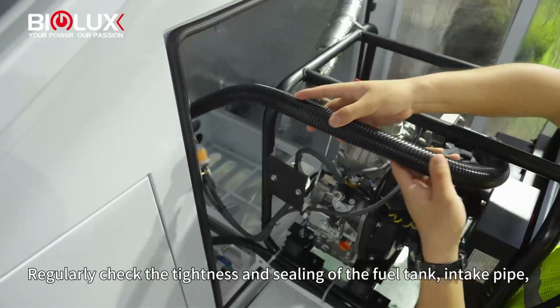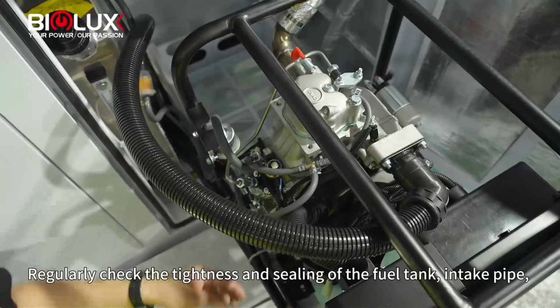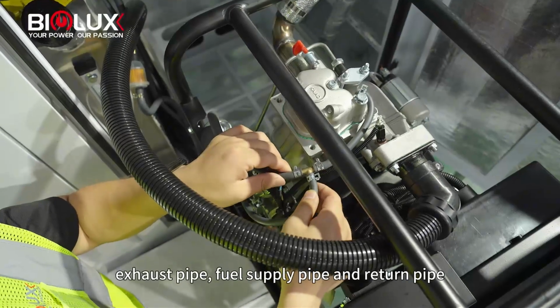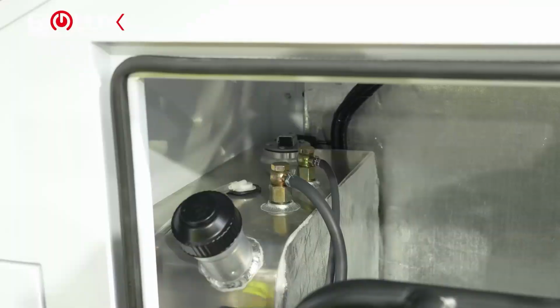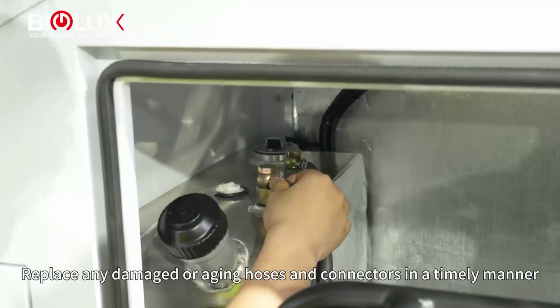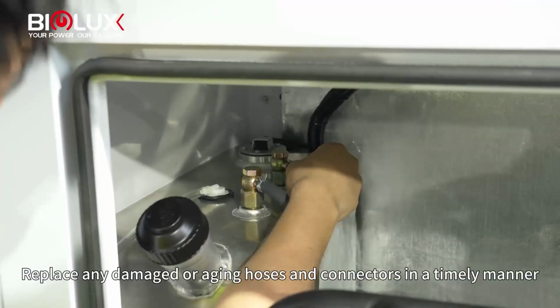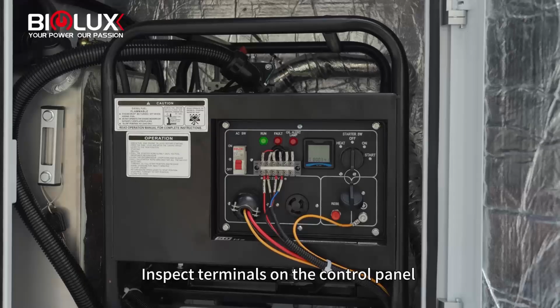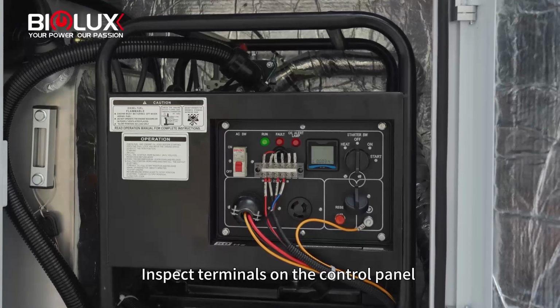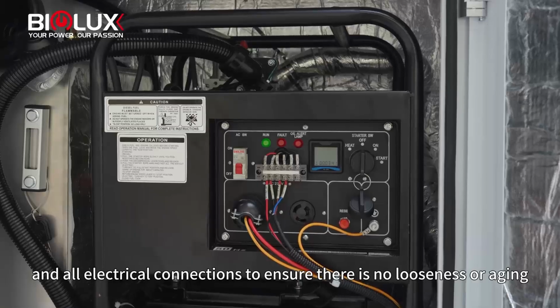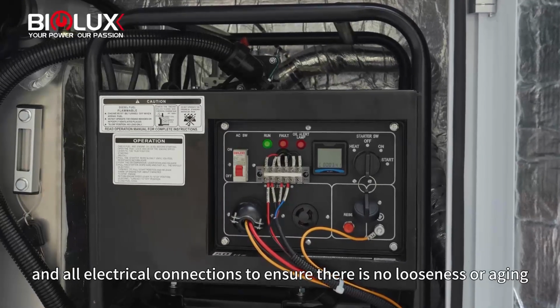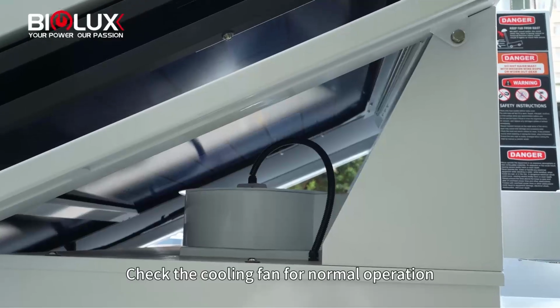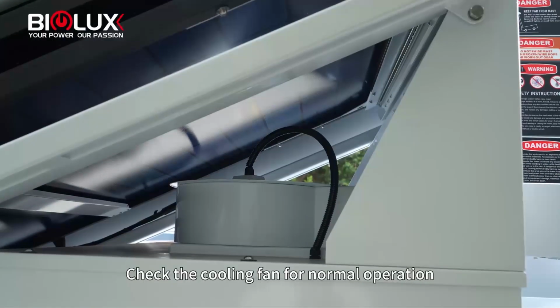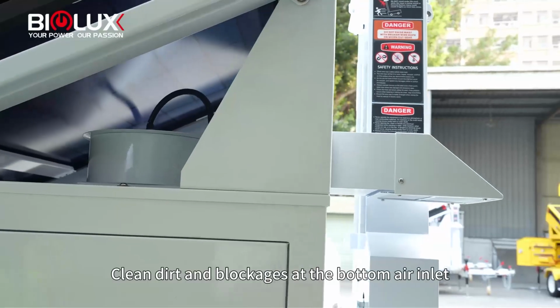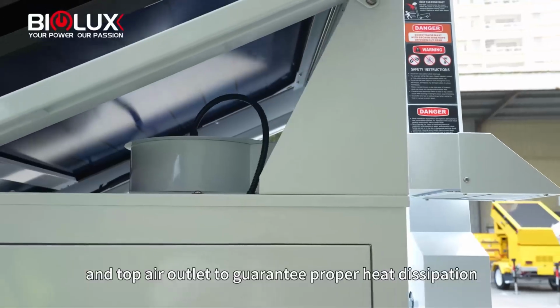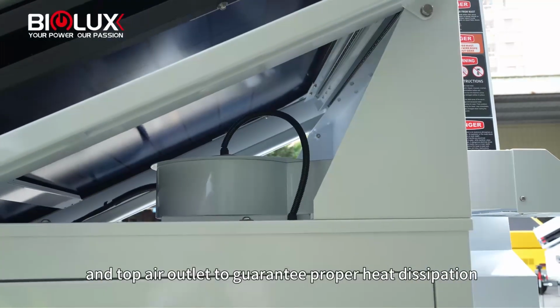Regularly check the tightness and sealing of the fuel tank, intake pipe, exhaust pipe, fuel supply pipe and return pipe. Replace any damaged or aging hoses and connectors in a timely manner. Inspect terminals on the control panel and all electrical connections to ensure there is no looseness or aging. Check the cooling fan for normal operation. Clean dirt and blockages at the bottom air inlet and top air outlet to guarantee proper heat dissipation.